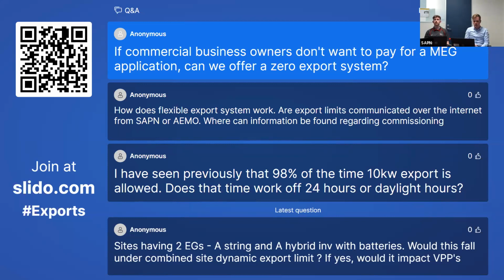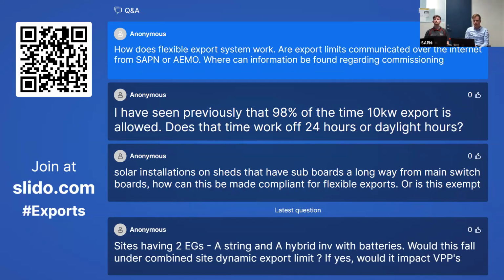Now, how does the flexible export system work? Are export limits communicated over the internet from SAPN or AEMO? Where can information be found regarding commissioning? We host what we call a utility server, which sits on the internet. When a flexible export system is commissioned, that inverter or gateway device is connected into our server. Every certain period of time, we calculate new export limits, which are then downloaded by that inverter over that internet connection from the server, all done based on standards-based communication using the IEEE 2030.5 protocol.